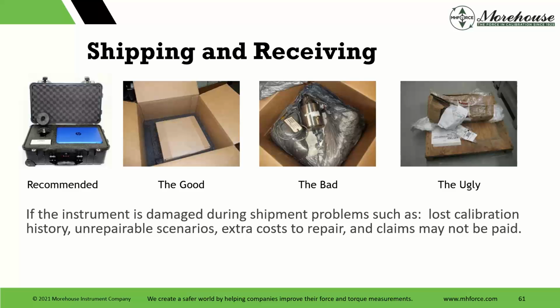And then finally, when you ship things, there's a couple more slides here. Look, these cases are not cheap, but they're not super expensive. And the cost for what's on the left is far less than when you have instruments damaged and you lose the stability or need repairs or you can't get your as received data. If you're not using control charts and process controls before it leaves, so that you know exactly how good your instrument was and you can validate it, you're in trouble if damage happens during shipment.